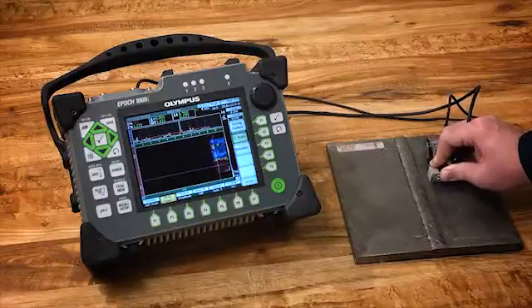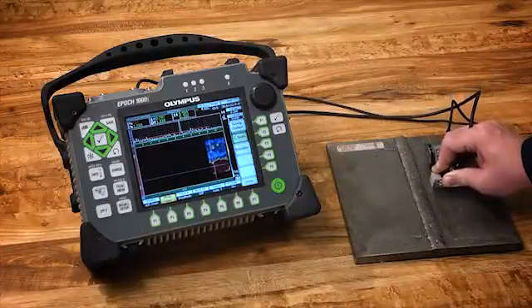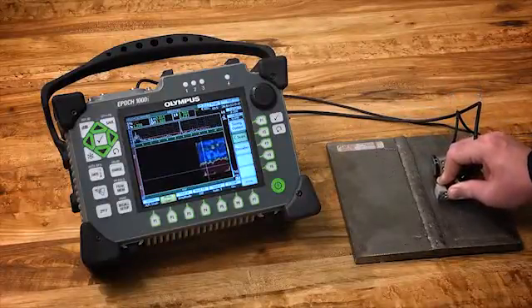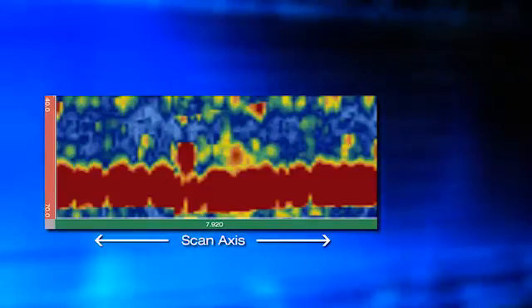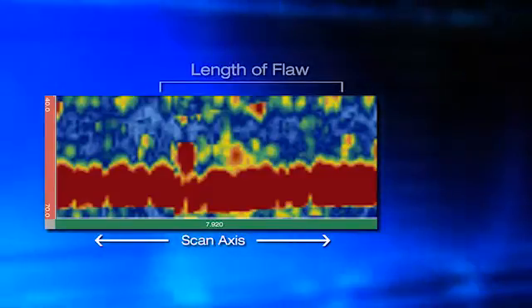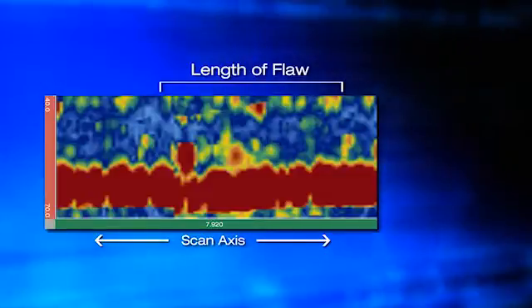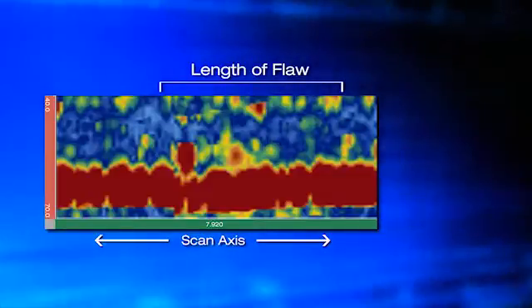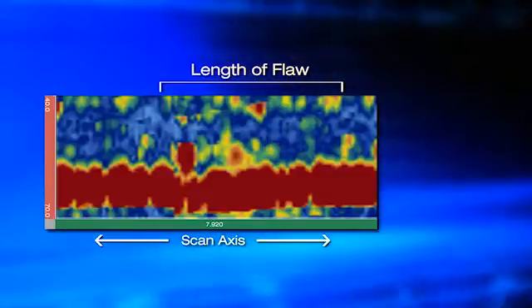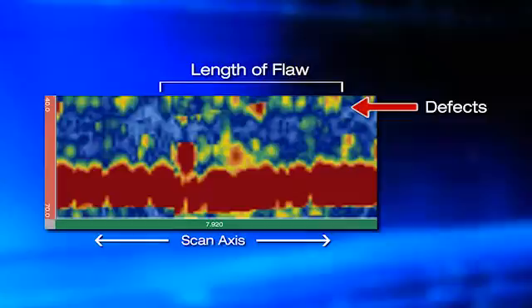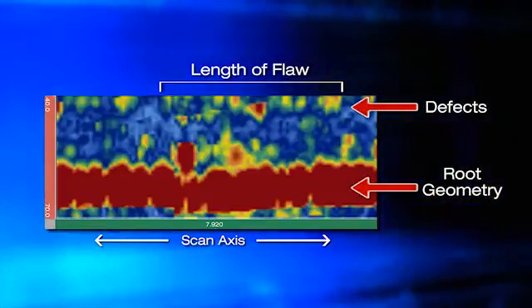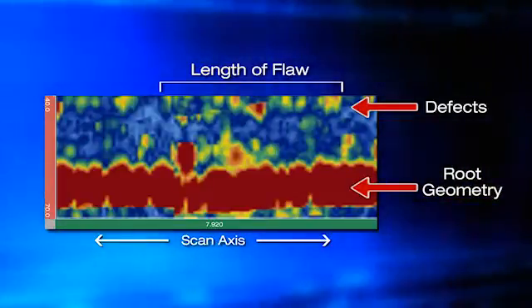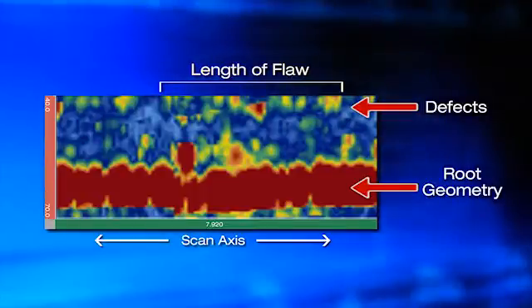This encoded C-SCAN capability adds an additional dimension to standard sector scans. The C-SCAN image allows you to determine the length of the flaw along the weld. It can also aid in differentiating between defects and geometrically induced reflections, such as those that often occur from the root of the weld.